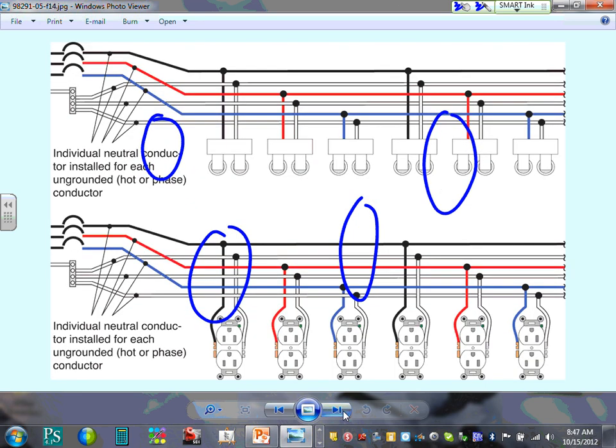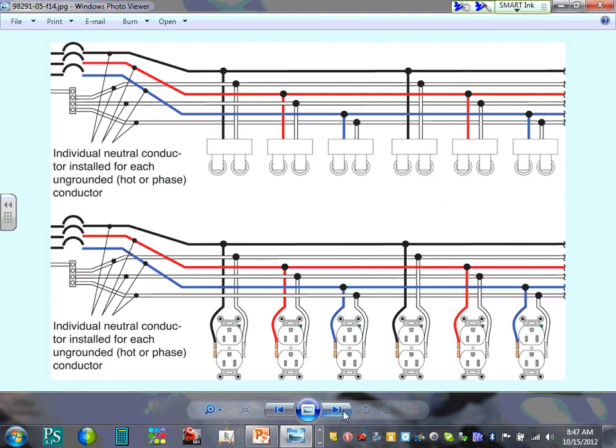Here's how you wire in a three-phase system. If you haven't done branch circuits, please pay attention to this, please. This is how we typically wire in a three-phase system, because you guys haven't done a three-phase, right? So you take a three-phase circuit here, basically. There is no multi-wire branch circuit. Can you guys see that? And we're feeding multiple receptacles. Later on with Chad, you're going to see we're going to feed 6 receptacles here. So I have 6, 6, 6, 6, 6, 6.